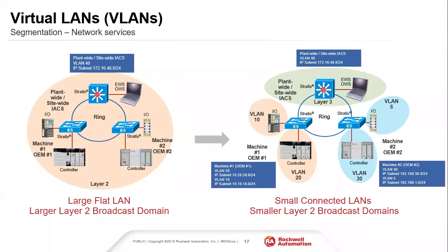Even if you have a gig topology up top. But the benefit there, and the reason why the managed switch network gets powerful, is, think of the segmentation stuff I was talking about. I now have point IO, which is at 100 meg. I have my IP cameras that might be at 100 meg. I have my ControlLogix that might be at 100 meg. But I now have a pipe that's a gig or more going to the top end network. So even though I might not be able to make that fast enough, because my pipe is large enough to take all of those strands of data and send them up, that's why you want to have that top end network be at a gig infrastructure.